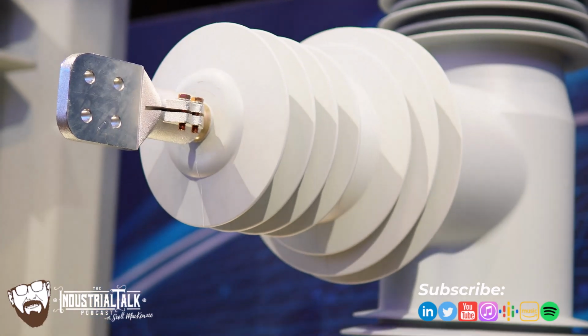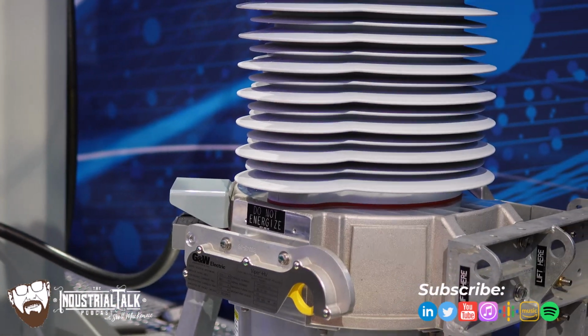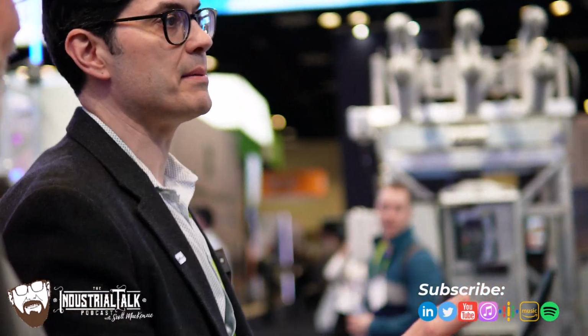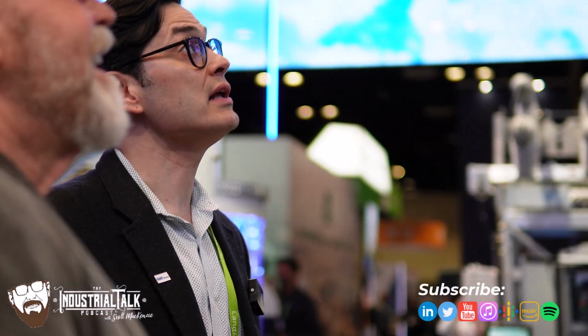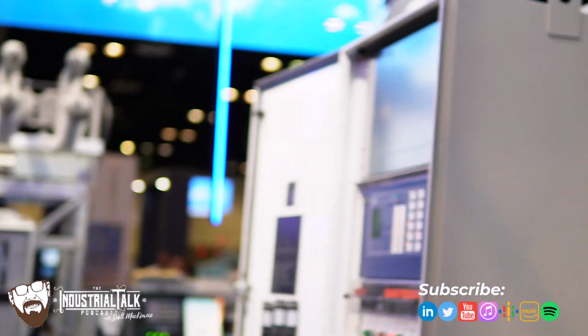But the thing to remember about this is that your current and your voltage are built into it. Okay. Right? So you've got integrated current sensing, integrated voltage sensing in this product. So you can mount it up on a pole. It's idealized for pole applications. It's inherently single phase, which allows you to install this in a variety of different structures at 72 kV, because there's a lot of variety in these structures, and you need to have flexibility to be able to mount these things wherever the power lines are. So we're seeing customers using this product for fault interrupting applications. Sometimes they just want to sectionalize outside of the substation. Yeah, absolutely. They don't necessarily want or need protection outside the sub, but they want to be able to break up those lines. So this is a fantastic sectionalizing device.